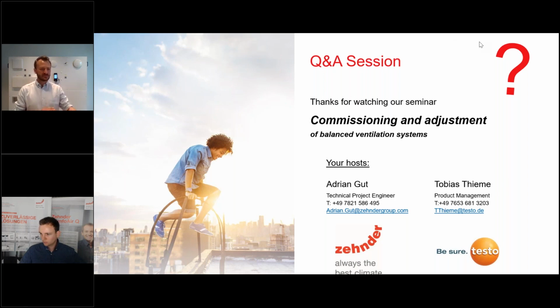From the accuracy, it's the same, but with this module, you are a little bit more flexible, because if you go to the ceiling or if you go up, then you can take the measurement, but you don't have to look at the display, because the display you can have here, or like you see on the wall in another instrument, and there you have also the possibility of creating reports and customer data and so on. And you have also the opportunity to connect other probes, other applications. But if you do only airflow measurements at outlets in the residential area, then 417 is a good device, definitely.